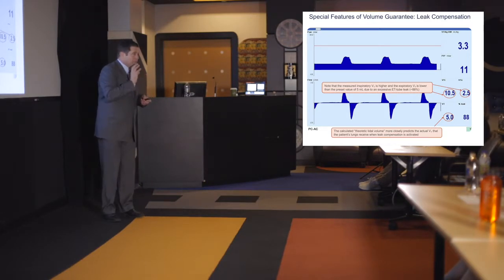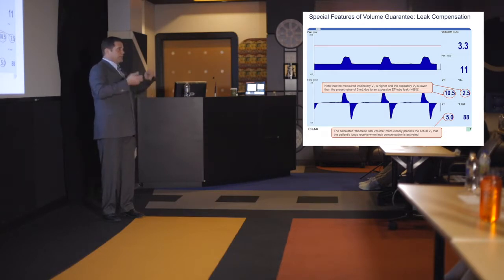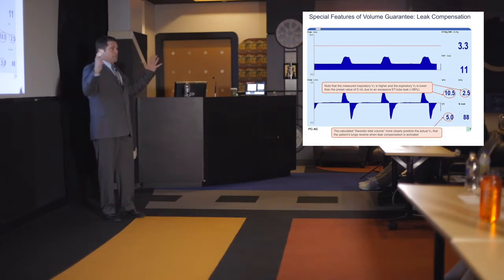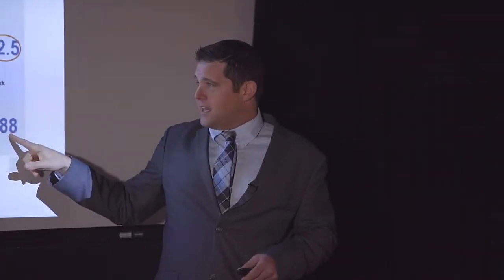Because if you take your PIP, your PEEP, your inspiratory time, your expiratory time, and you look at the leak flow that you're losing, take all of that and put it into an algorithm, the ventilator will adjust the pressure based on what it thinks it's giving the baby. And this can work up to about an 80% leak. So this is an 88% leak.